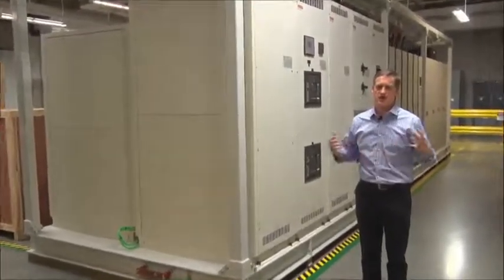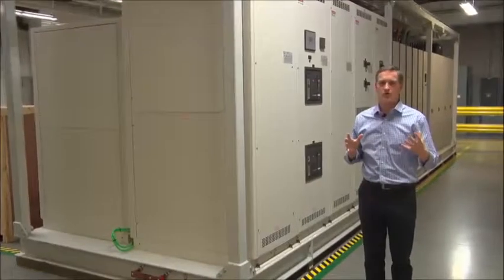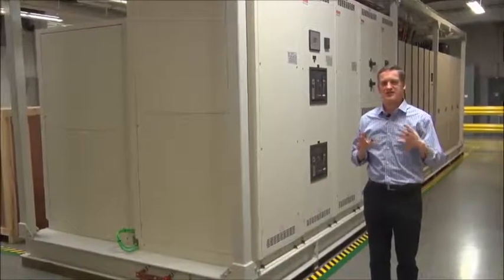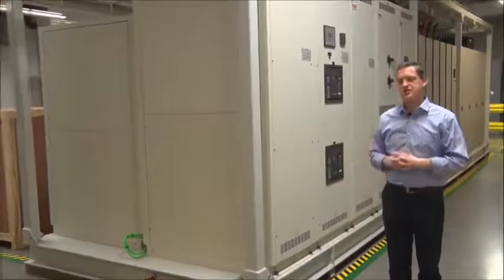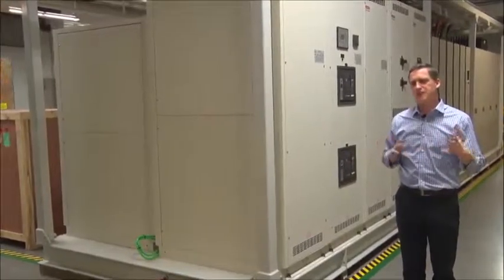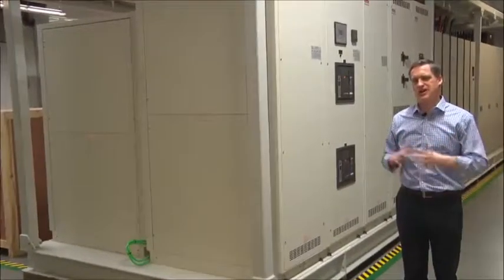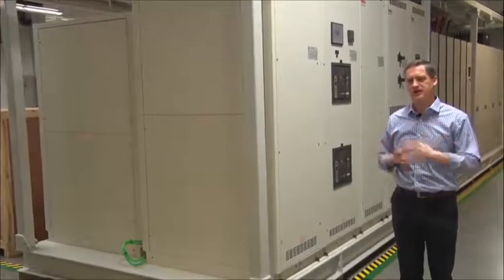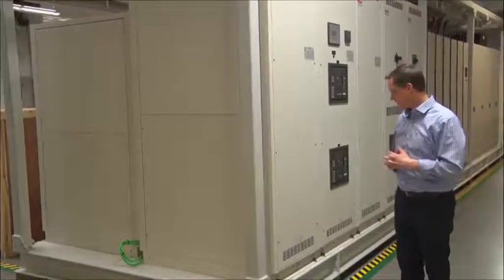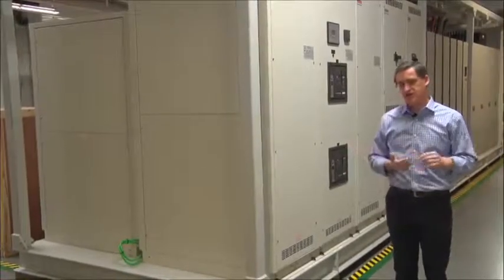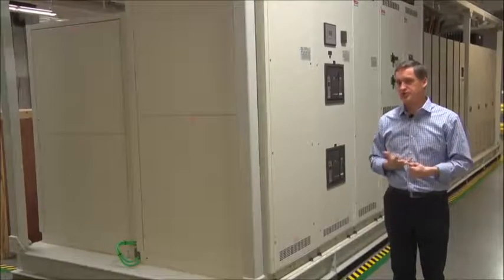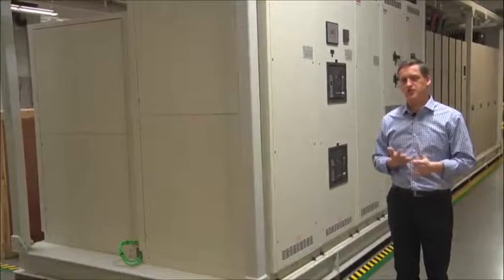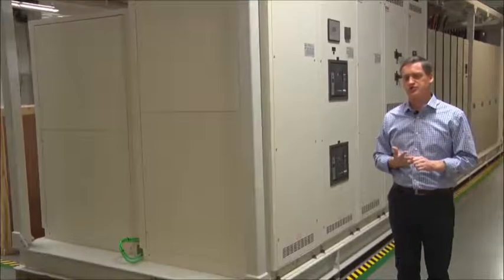So the power module designs, even though there's not a lot of equipment specifically on the skid, there's a lot more complexity in terms of how it's designed and the variations and options we can include. Again, what's on it is UPS, typically LV switchgear, but it could be medium voltage as well. We've done some medium voltage solutions.